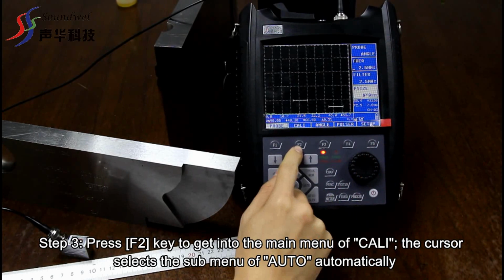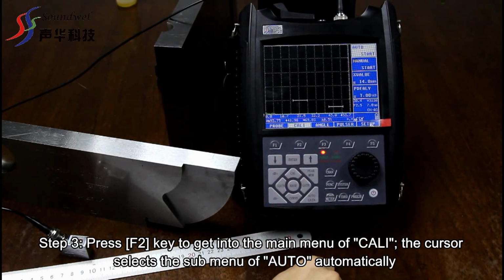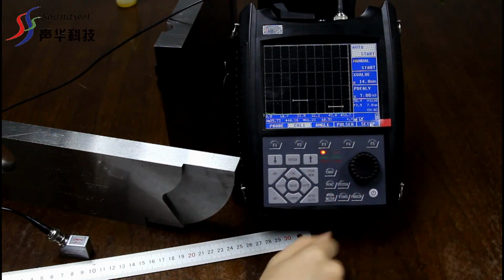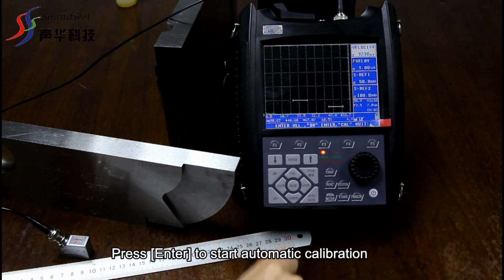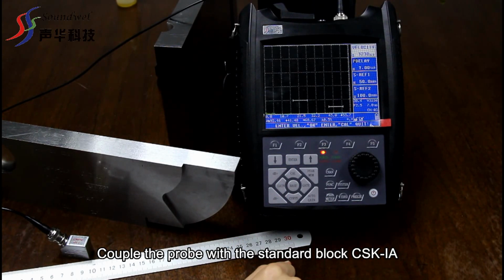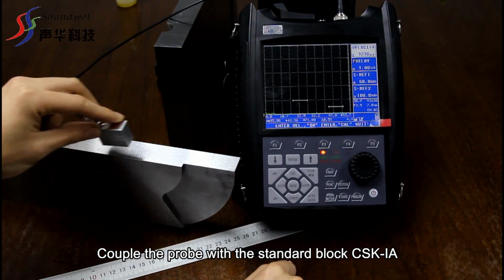Step 3. Press F2 key to get to the main menu of Cali. The cursor selects the submenu of Auto automatically. Press Enter to start automatic calibration. Couple the probe with the standard block CSK-IA.